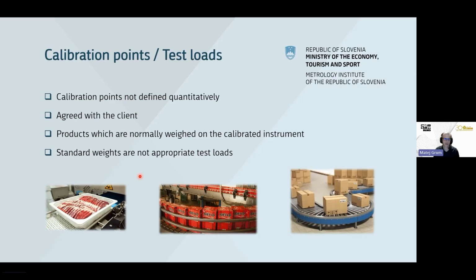It is not good practice to use standard weights to calibrate such kind of instrument, because it usually happens that with the same nominal mass you can get significantly different response of the instrument, which is then related to the shape of the product, length of the product, orientation of the product on the transport system, and so on.